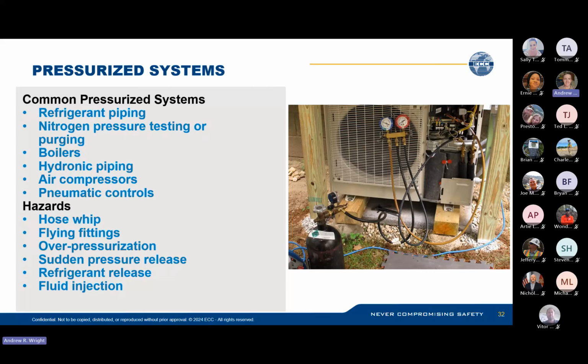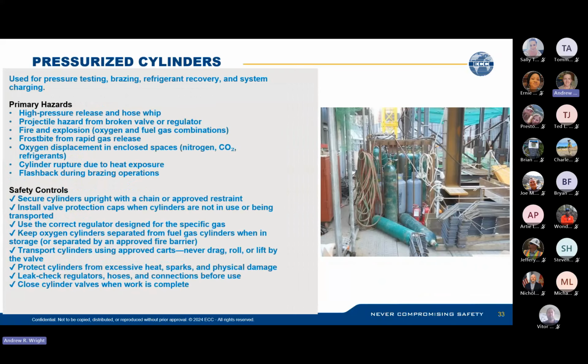All right, hazards: hose whip, flying fittings, overpressurization, sudden pressure release, refrigerant release, fluid injection. You've got high pressure hose lines and connections that don't cope well with exposure to skin. Pressurized cylinders, as you can see in the picture here, there are some cylinders not being stored correctly. I don't know if that's oxygen or whatever, but they use cylinders for pressure testing, brazing, refrigerant recovery, and charging the systems. So you've got high pressure release and hose whips, and projectile hazards from a broken valve.